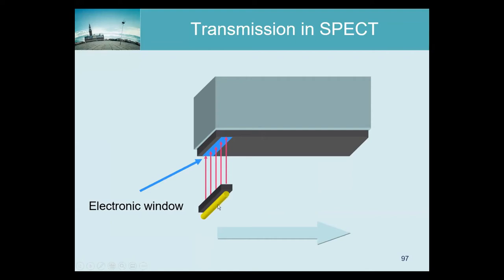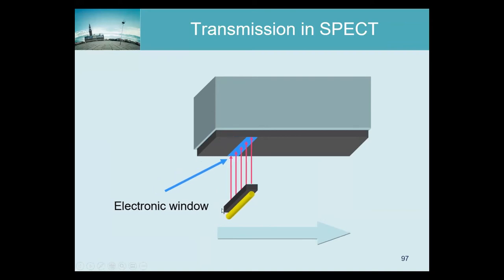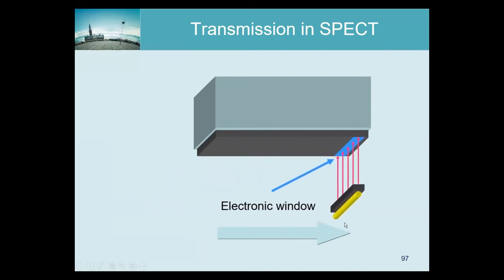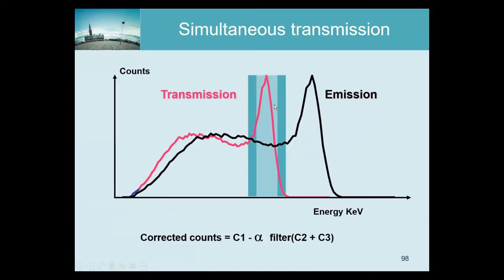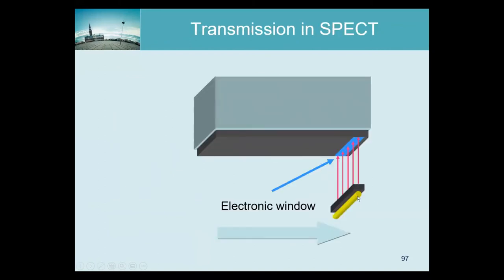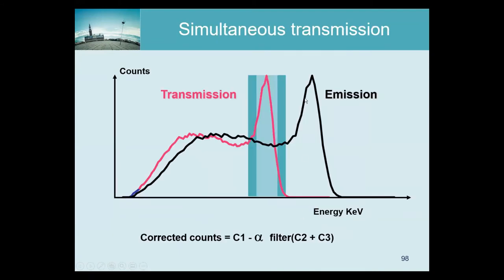Here is one of the clever ideas. Suppose you have a radioactive line source — a long-lived tracer — and you put a collimator in front such that the source can only send photons through a small spatial window. Then you scan that window from left to right. Because there are collimators on both sides, you can put a significant amount of activity there so that many photons are caught. In SPECT we have multiple energies, so we can put a different isotope in the transmission source than is used for the tracer.